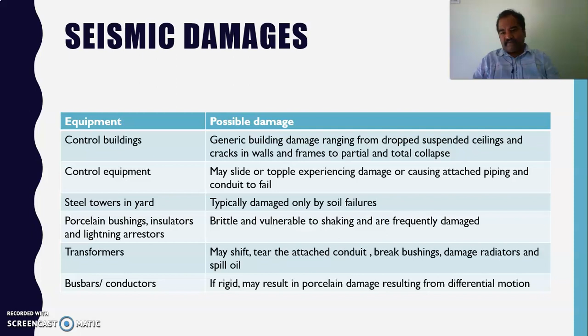There will be transformers too. Their radiators may get damaged, their bushings may be broken, and the oils inside their tanks may get spilled out, along with damage to any wirings attached to them. So all the conductors and bus bars, if they are rigid in structure, may result in porcelain damages because of differential motions.